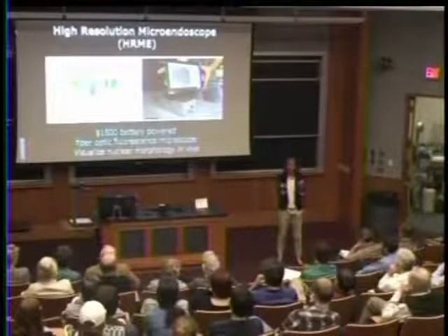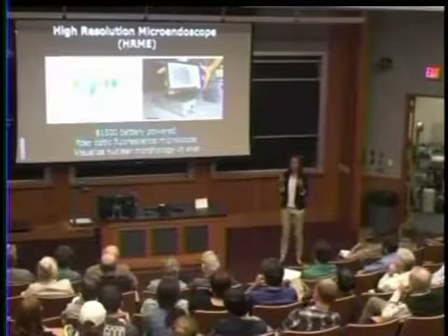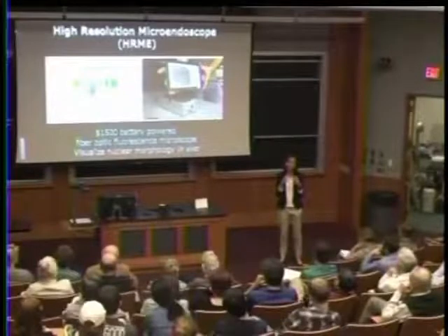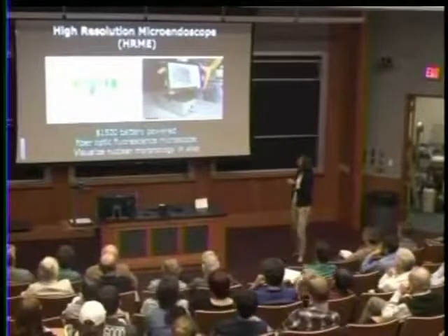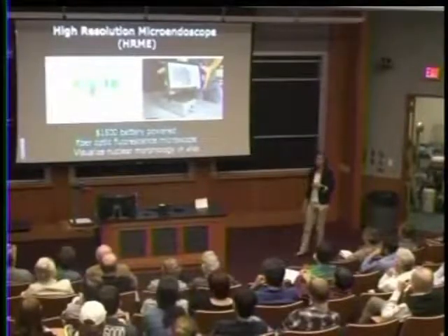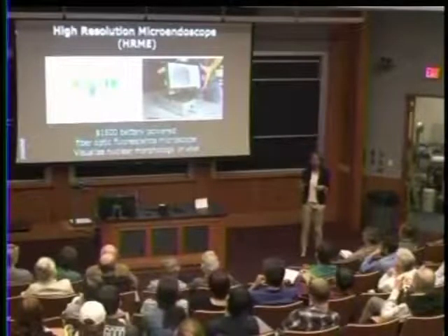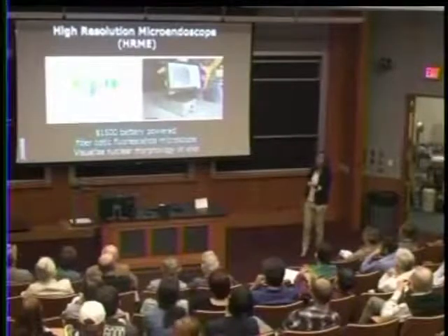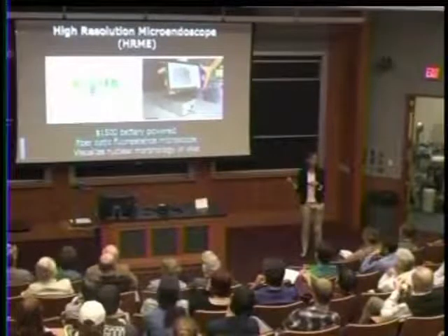That's easy to look at in a biopsy. What we have done to try and look at that right at the point of care when the tissue is still in the cervix is we've developed a fiber optic fluorescence microscope. And you can see the device right here. It's run with a tablet computer. And inside here, essentially, you've got a blue LED that excites the fluorescence. You've got a filter cube to direct your excitation light to your fiber optic probe, and then to direct the emitted fluorescence onto a very inexpensive CCD camera.